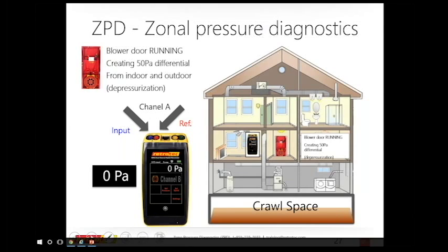The key really is, we're looking at absolute values, and again, we've got that 50 pascals of air barrier, and we're just kind of looking for how much of that air barrier we've crossed. If we haven't crossed all of it, then there are leaks, there are pathways that we don't want. Right. So by absolute value, it's basically the difference between 0 and a number. So negative 50 is an absolute value of 50, and 50 is an absolute value of 50 because you're 50 units or Pascals away from 0.